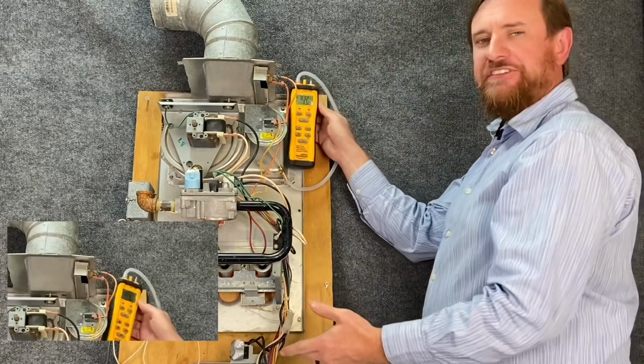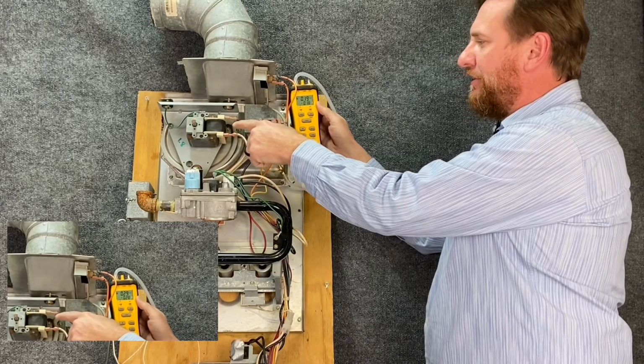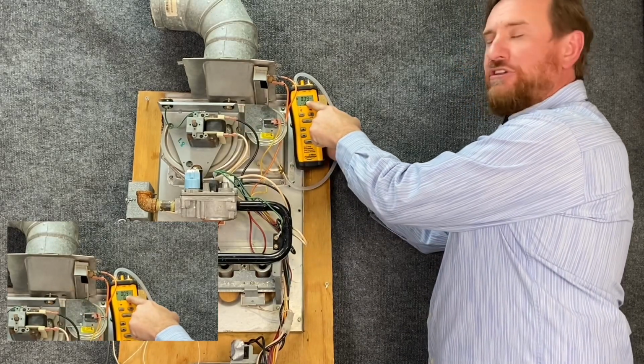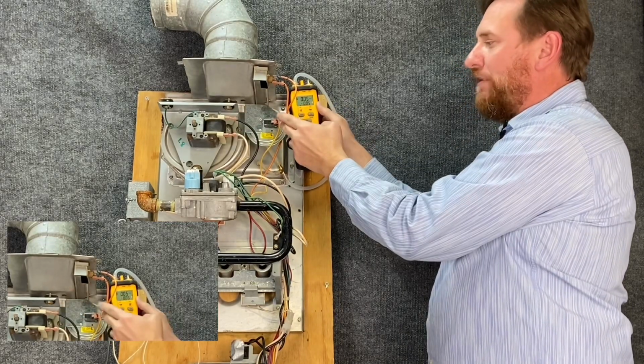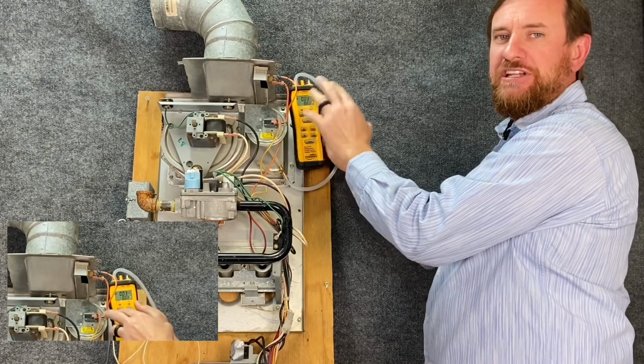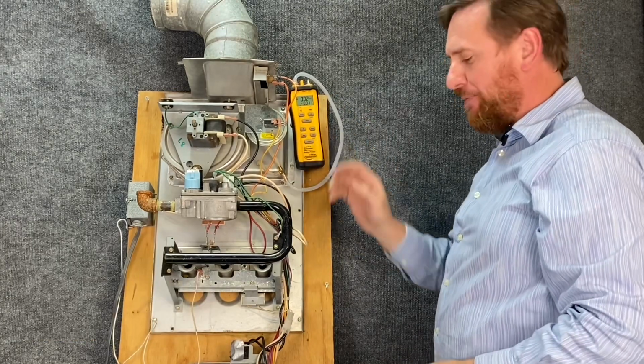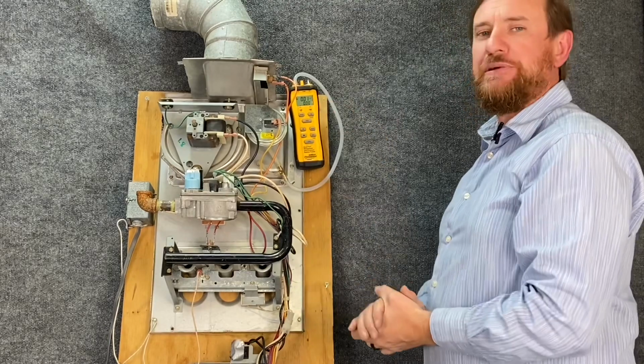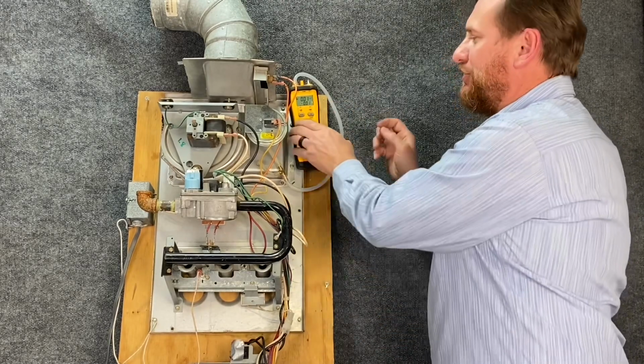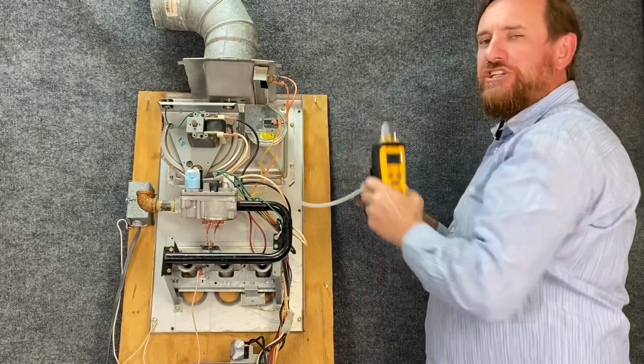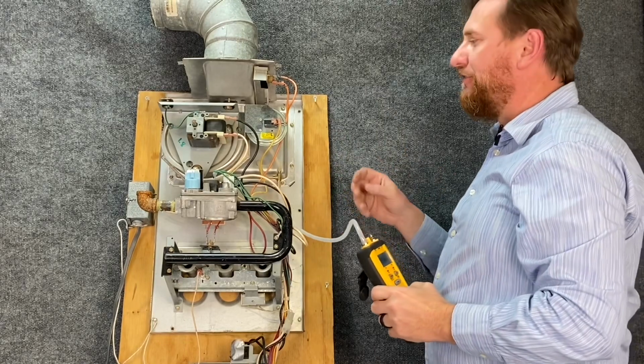As I cycle the system off, my inducer fan motor cycles down and I start losing my vacuum. The switch then goes back to its open position. It knows that it should be open. The control board knows that it should be open. Everything is working correctly, as it should. That's one way to check the switch. There is, however, another way to check it.